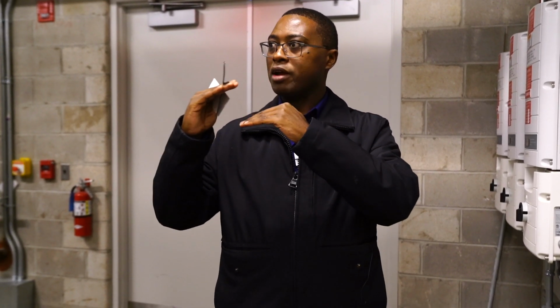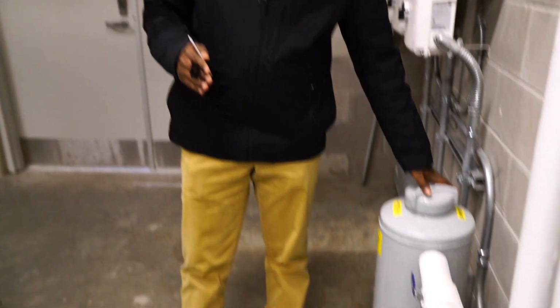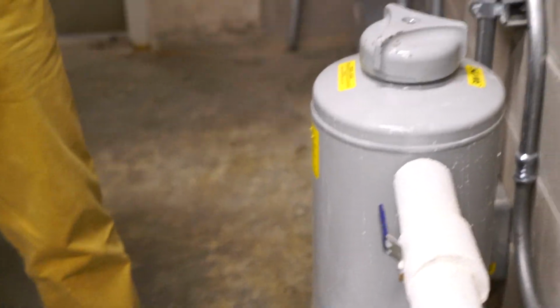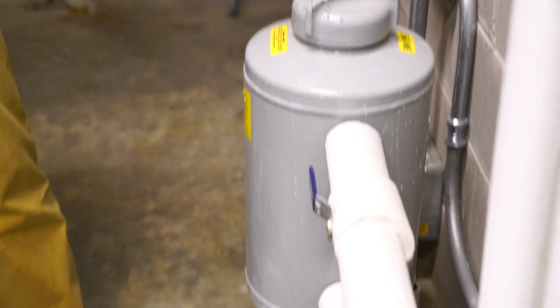It's a one-time shot, you don't have to add chemicals again. Not forever though - if you have a leak, your chemical residual goes down and we'll come back. We're here every month to check that residual, to make sure it's meeting the right parameters and within the range we recommend. If it drops, we'll add chemicals. If it stays the same, we won't do anything, but we'll make you aware. So this is a chemical bypass feeder for your hot water heat system. Any questions? That's it.